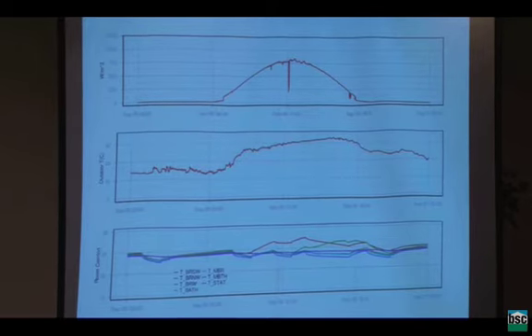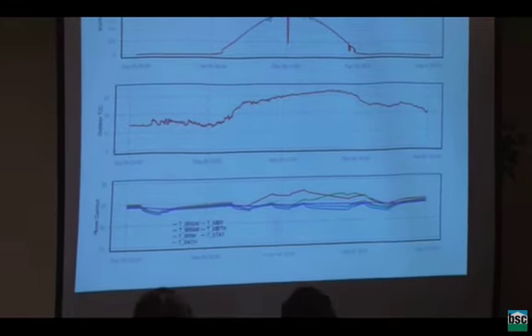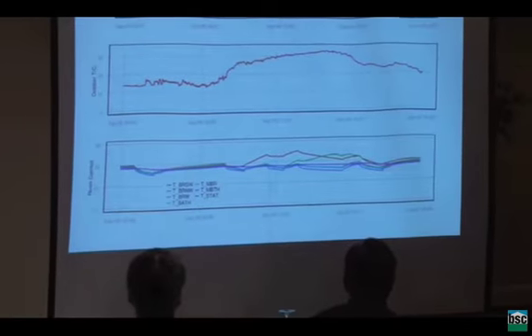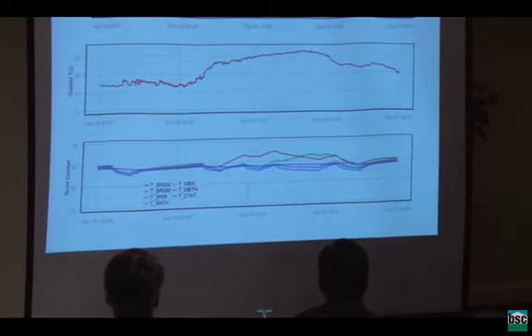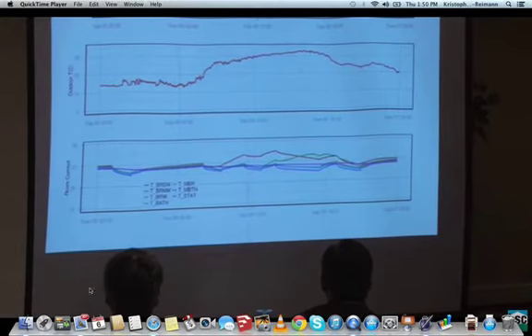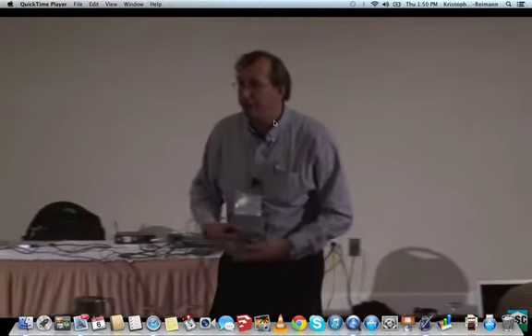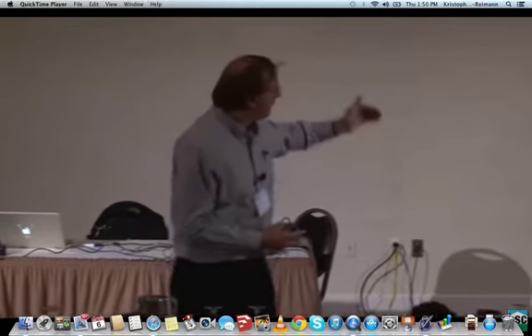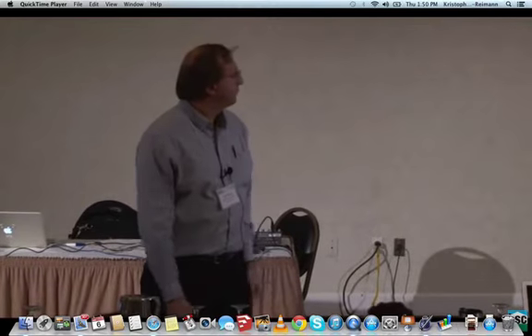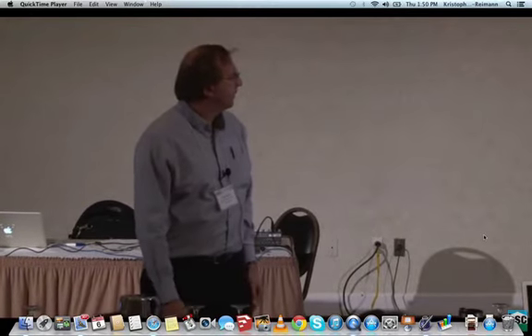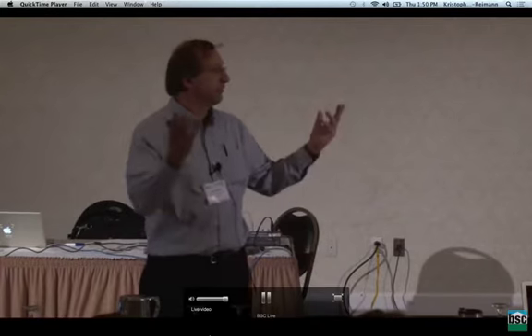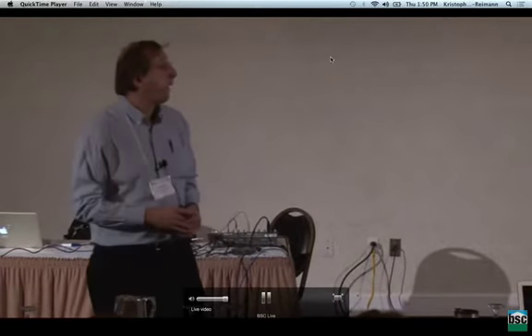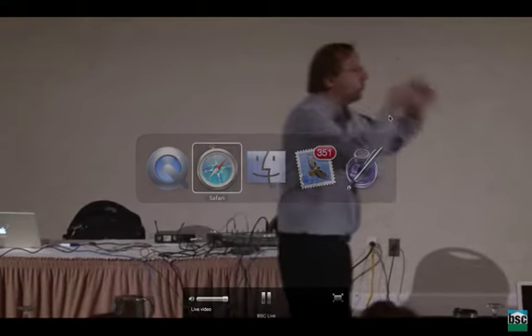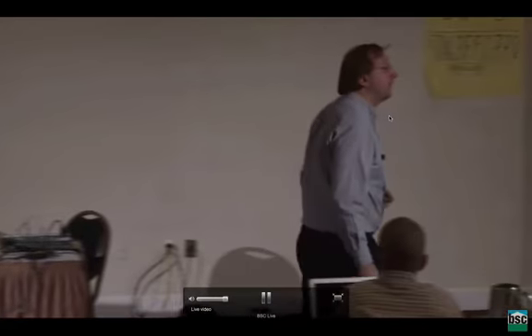And so we see temperatures there deviating by almost 6 degrees Celsius, which is something like 9 or 10 degrees Fahrenheit at the peak. And the peak temperature is getting into the 80-degree land in that southwest bedroom. And it drops off later in the day, and by the evening it's back down to 76. And this is with doors closed with just a basic undercut, nothing huge.